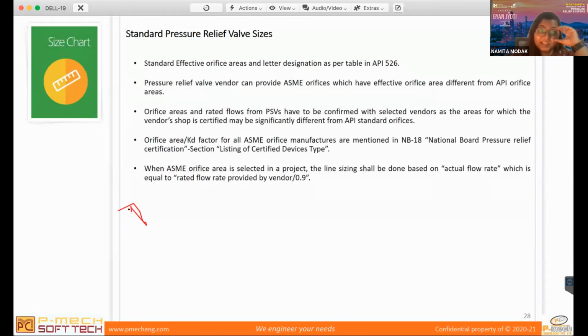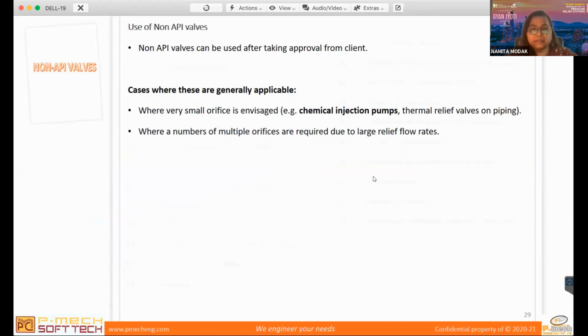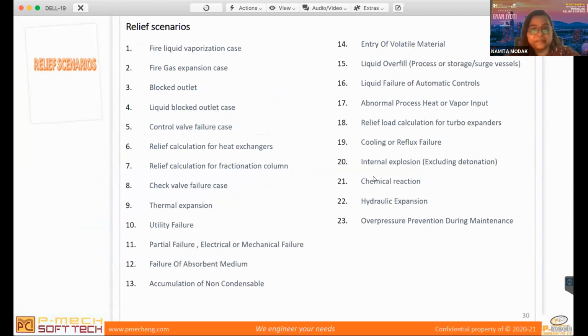So as I said, there are standard pressure relief valve sizes available in API 526, which will be helpful after calculating the orifice sizes as per API 520. You can refer to this table. There are also some scenarios where you use non-API valves, which is vendor specific. For services like chemical injection pump, thermal relief valves on piping, you use non-API PSVs.